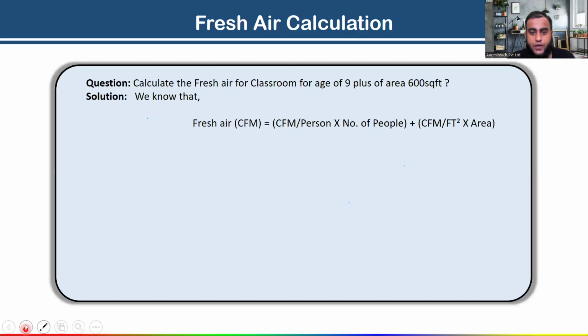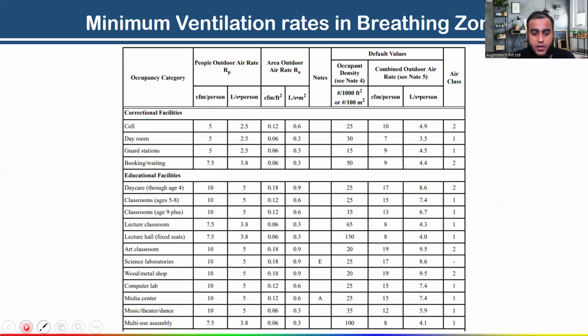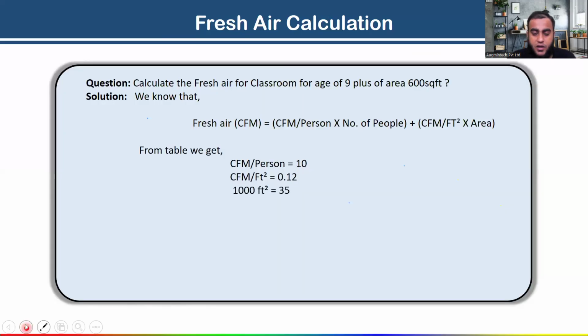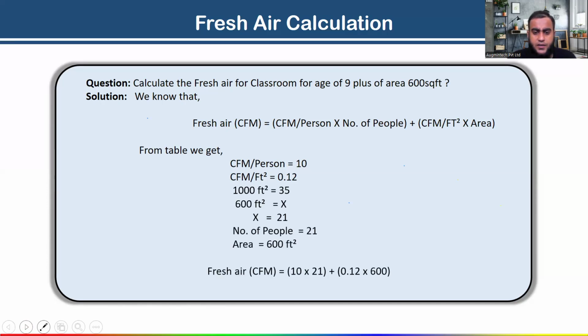Now I am substituting these values in this formula. From the table, what CFM per person value have we got? 10. Is it clear? And next, CFM per square feet 0.12. From this table, same way, as I told you, for 1000 square feet it is 35, so for 600 square feet we have got 21 people. Now just substitute all these values in this formula, and you will get 282 CFM. For the classroom plus 9 ages students, how much fresh air is required? 282 CFM. So the exact calculation is this. Now I think all of you are clear on the fresh air calculation.